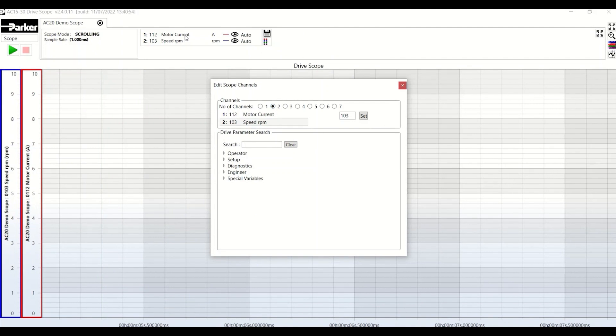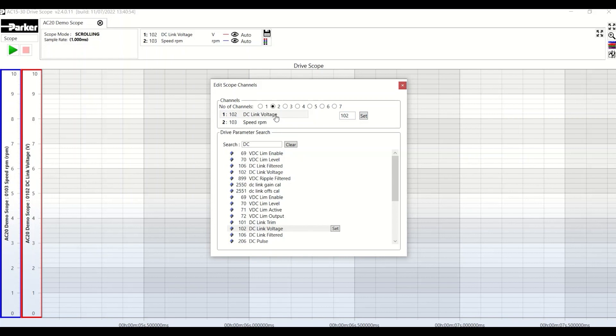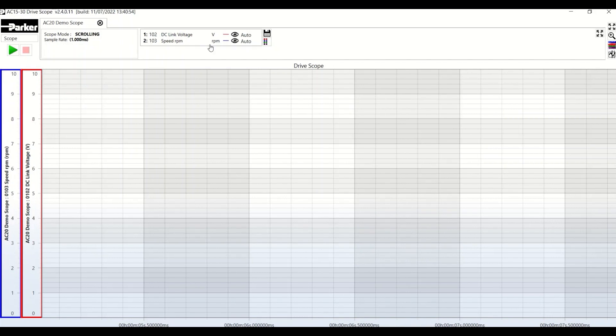At the moment, you can see the motor current and the speed in RPM, but these can be changed easily. For example, I can select the motor current channel and select DC bus voltage in its place. Typing DC into the search allows me to select DC link voltage, or parameter 102, which is displayed here. Click on set, and it is set for channel 1. So, channel 1: DC bus; channel 2: speed in RPM. Then close the window.